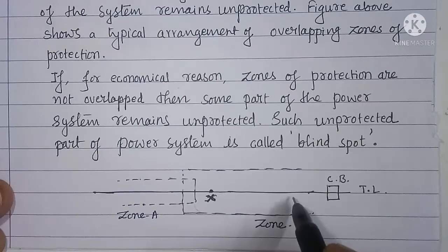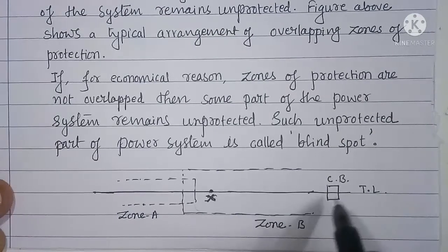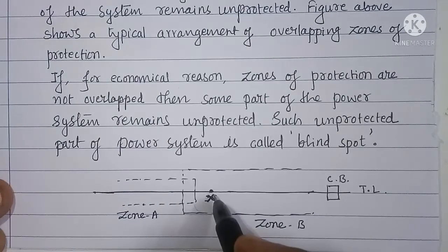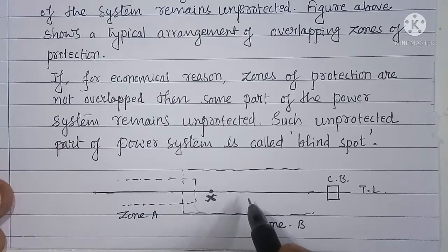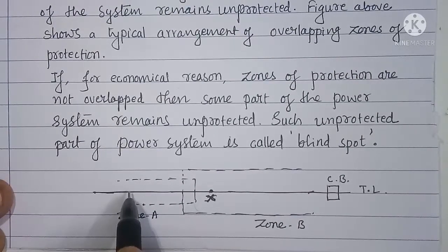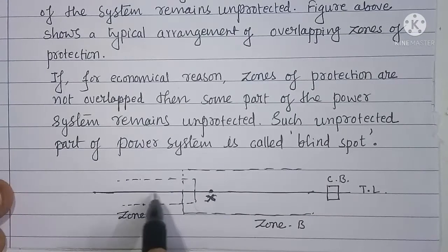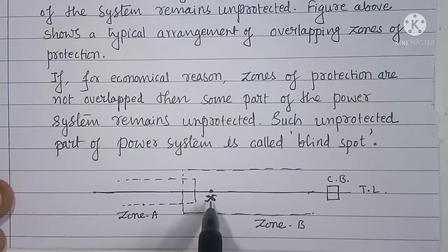That means there will be discontinuity in transmission line and hence no current flows to point X from the right side, but from the left side of this point X the current will flow into the point X, though there is a fault. That means zone A is not detecting fault occurring at X, and hence this X becomes the blind spot in the power system, as there is no overlapping of two protection zones A and B.